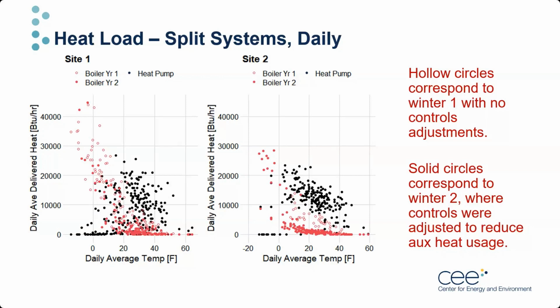We found that, out of the box, controls were not necessarily optimized to reduce boiler usage in mild temperatures, and this is most evident at Site 2, where we've marked data using the default control settings with hollow red circles from the aux boiler. And the filled circles there show data from after we modified the control settings to better prioritize the heat pump. And as you can see, that drastically reduced the boiler usage above 0 Fahrenheit. Next slide.